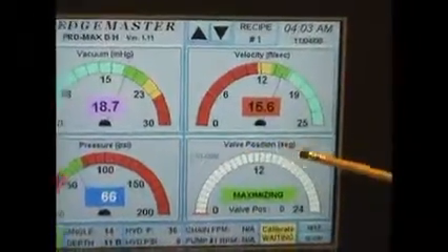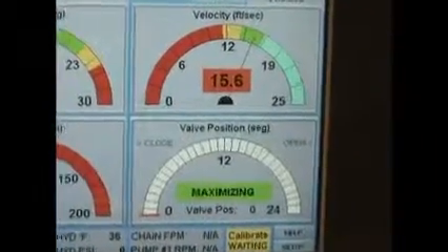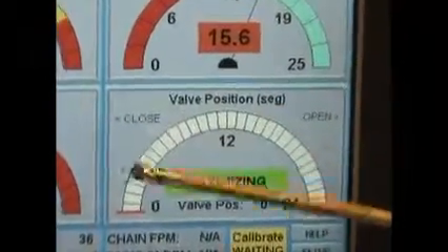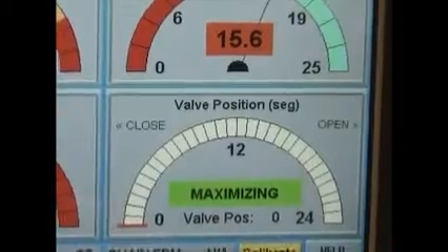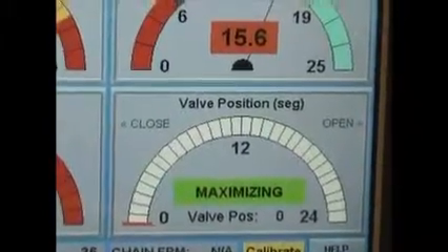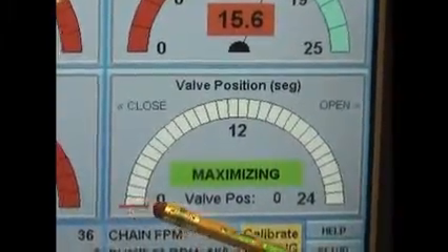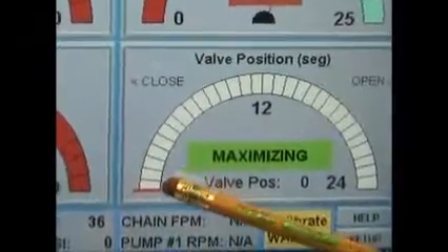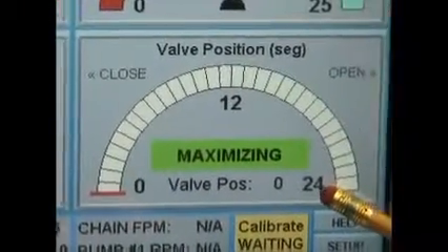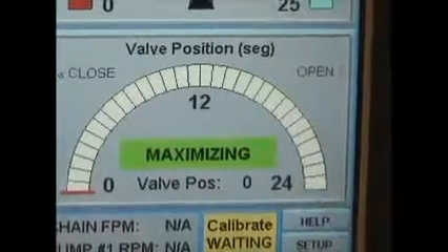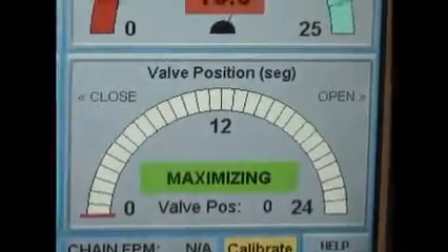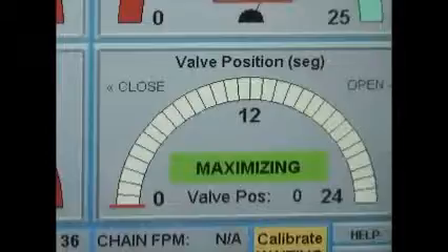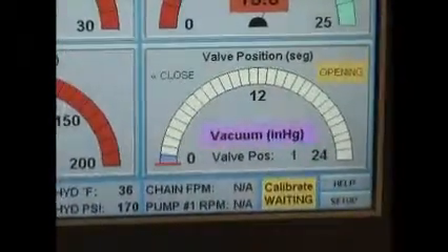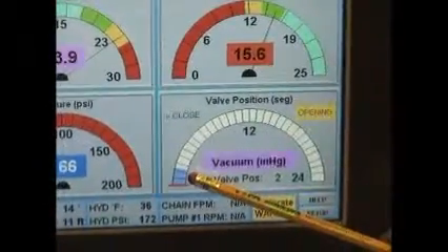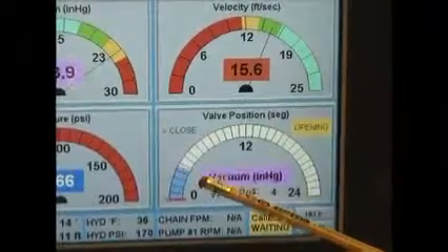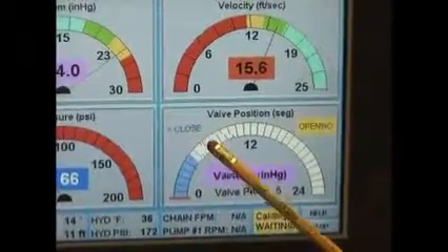This is the valve position. This tells how far the valve is closed or open under the water. This is what we call our freshwater production valve. 0 down here at the far left represents closed, and if the valve moves over to the high side over here, it would be fully open. As you can see, as we step this valve open, our blue line starts to increase. The valve is starting to open up. It will continue to open up.